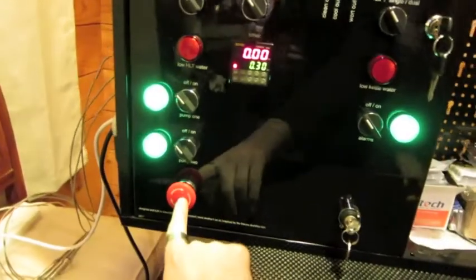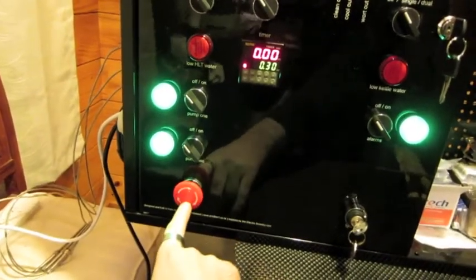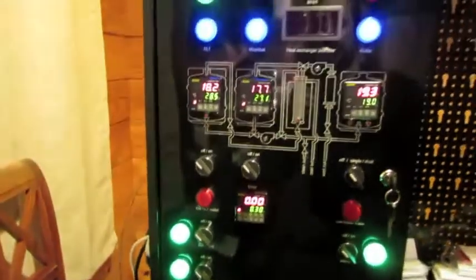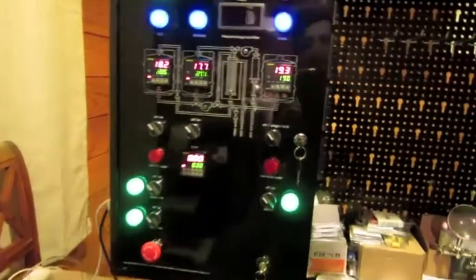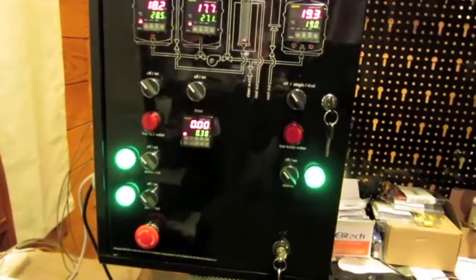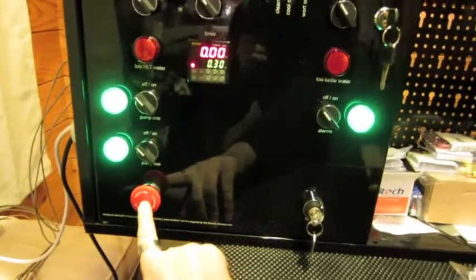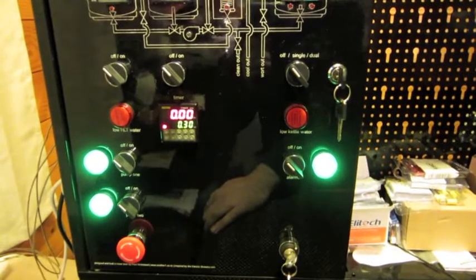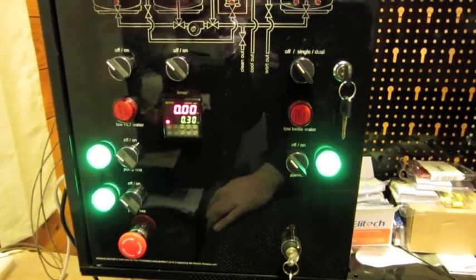I have an emergency button here which cuts off the power, and it cuts off the power via a solid state relay inside the unit to all the elements, or actually to another bank of solid state. Actually this cuts it off to a pole relay, a mechanical relay, and there's mechanical relays in front of all the solid state relays as well.